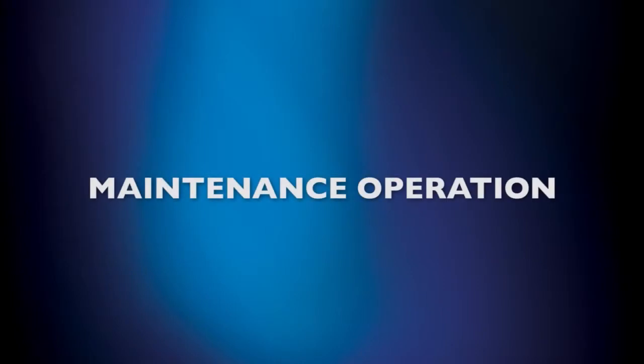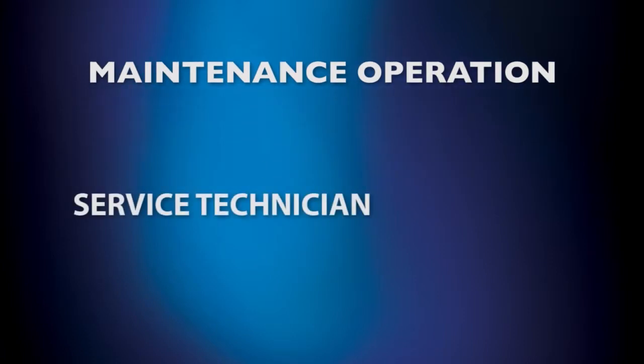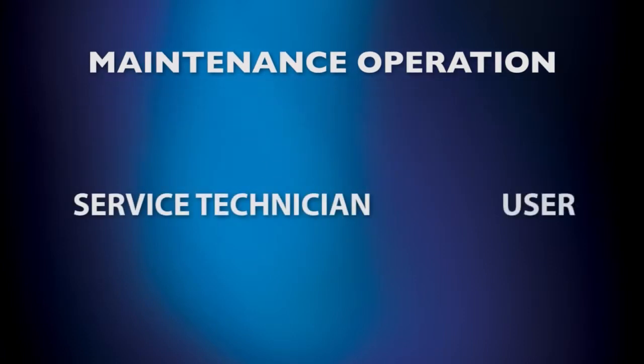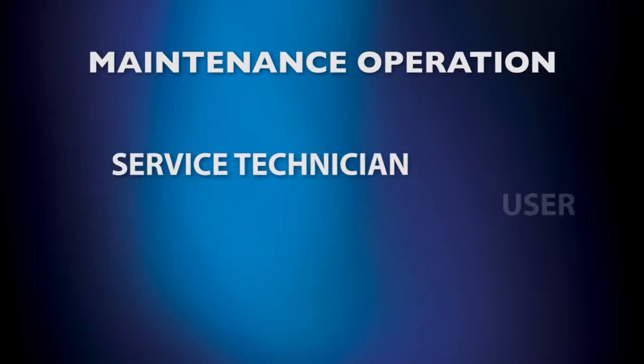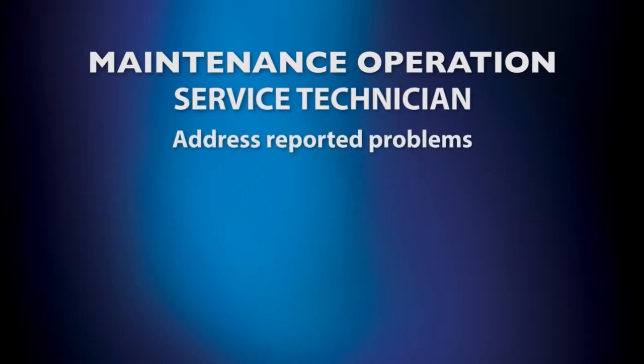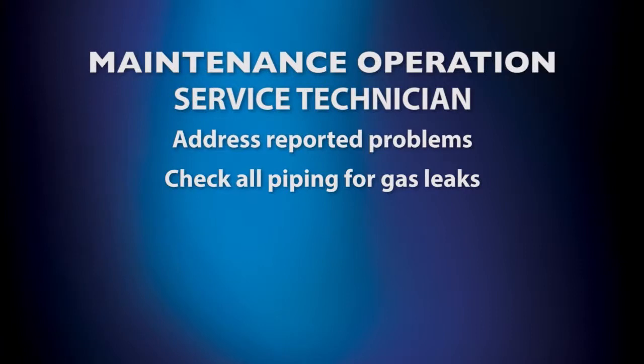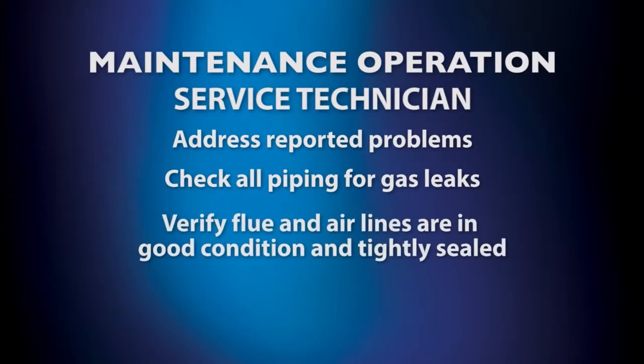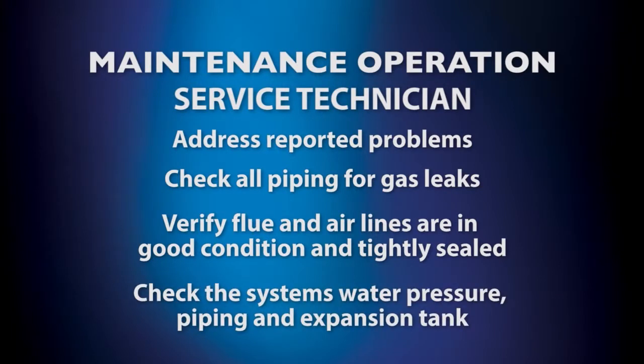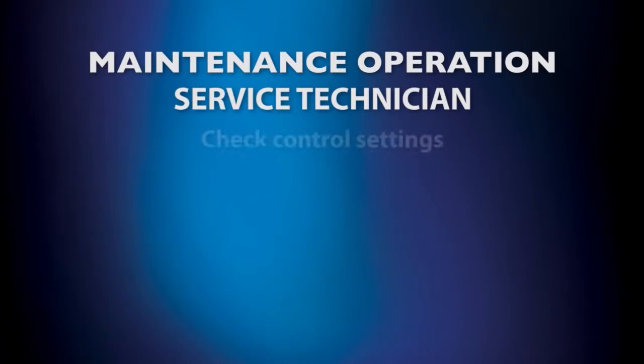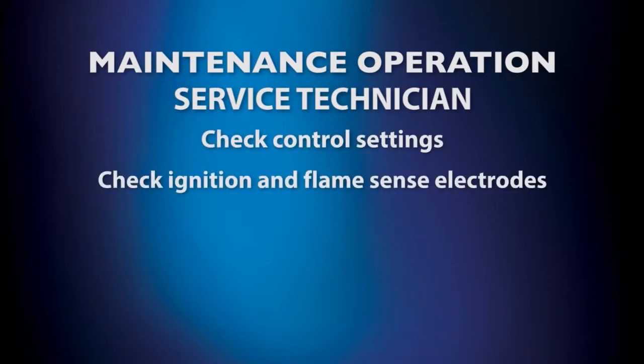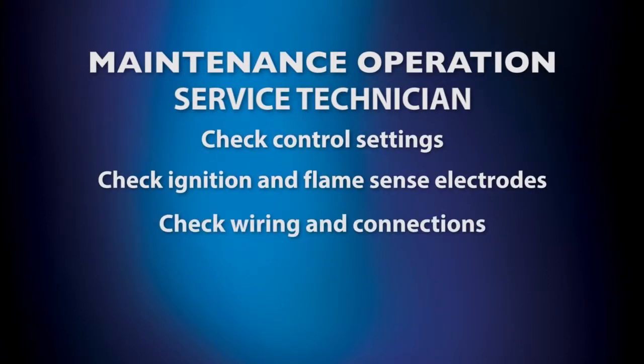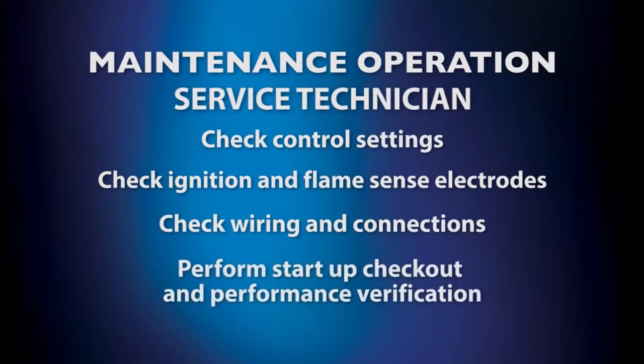The following maintenance operations have been separated for you into two categories: the maintenance schedule for the service technician's annual startup and the schedule for user maintenance. For the service technician's annual startup, address any reported problems. Check all piping for gas leaks. Verify flue and air lines are in good condition and tightly sealed. Check the system's water pressure, piping, and expansion tank. Check control settings. Check ignition and flame sense electrodes. Check wiring and connections. Perform startup checkout and performance verification.